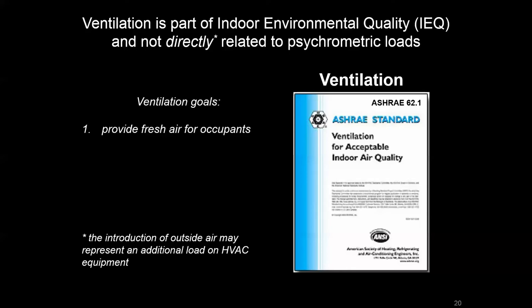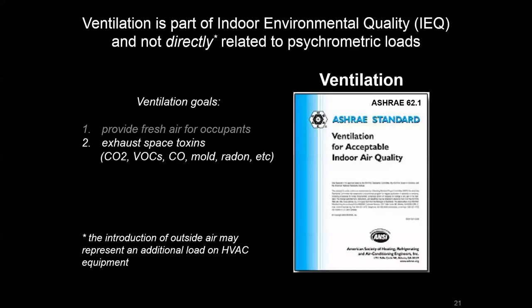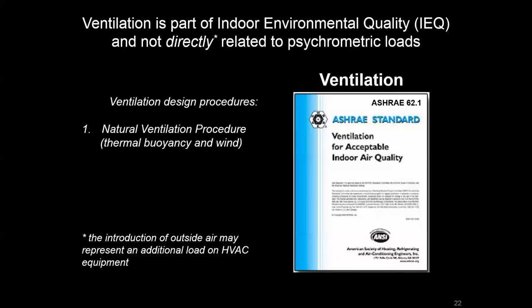The goals of ventilation are to provide fresh outdoor air to occupants and address any toxins that may be building up. ASHRAE 62.1 is the standard that predominantly helps us determine how much outside air ventilation needs to be brought in. It offers a couple of different calculation methods. The first is natural ventilation, which is rarely used because a lot needs to be known about the wind dynamics of your site, and you have to carefully design your entire envelope and architecture to support thermal buoyancy by creating heat stacks.